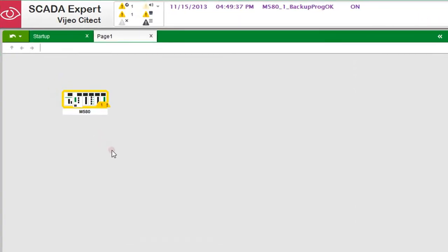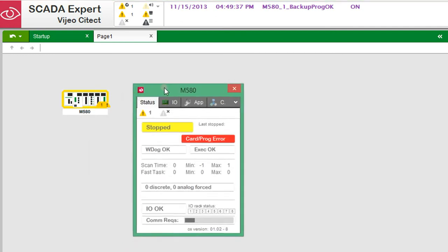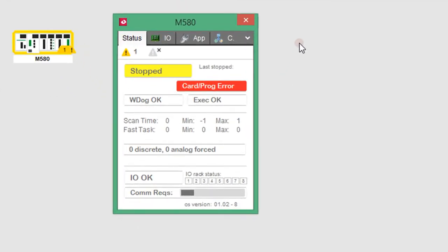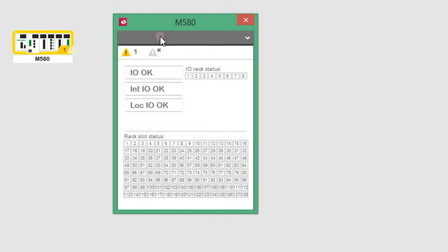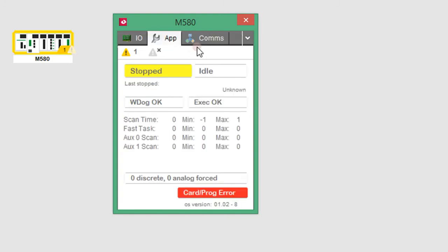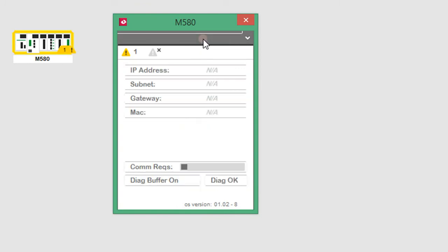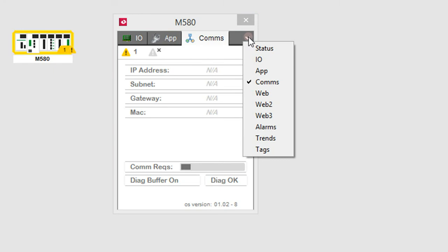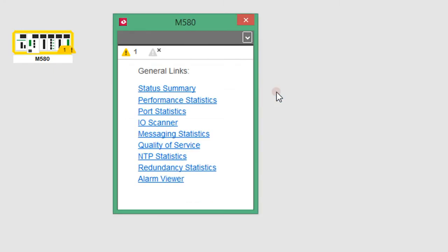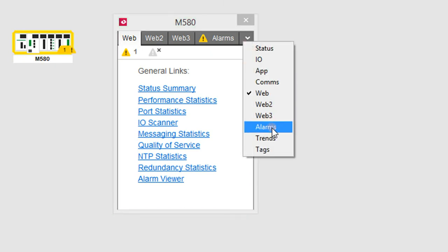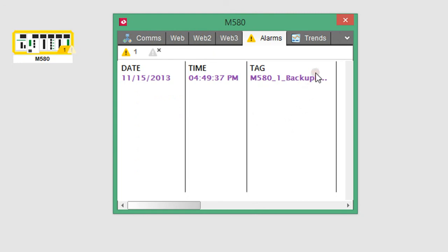The alarm border is showing that the PAC is either stopped or has an internal error. Clicking on the PAC will display the in-built diagnostic pages. The first page shows a status summary — the pages are designed to only highlight abnormal operation. The I/O page shows a detailed view of the communication racks. The app page shows the details of the PAC execution cycles. The comms page shows the communication status. The web pages show hyperlinks to the internal web pages of the PAC. The alarm, trend, and tag pages provide a detailed view of the diagnostics of the PAC.